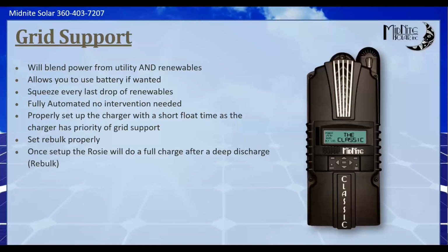Or if you set the state of charge lower, of course, it will bring the battery down to that state of charge. So if you set it for 50%, like I do here, and we'll do in our example, then if the battery's at 90%, all the loads will come out of the inverter because it will pull the remaining from the battery until the battery falls to 50%, and then it'll maintain that 50%. It does allow you to use the batteries we just mentioned, and it really does squeeze every last drop of renewable out of the system, whereas like an LBX mode or a time transfer mode, you can end up leaving some on the table depending on how full you want your battery.